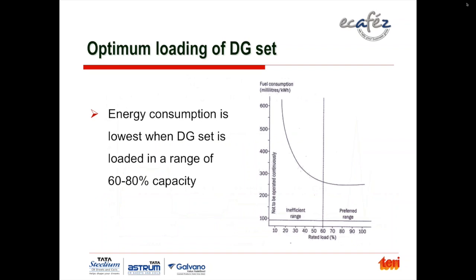Now, optimizing loading of a DG set, and I'm sure most of you are using DG sets now. A DG set essentially becomes very inefficient when it's underloaded. As you can see from this graph, when the loading is below 50% in the DG set, the specific energy consumption becomes very high, as the graph rises very steeply.